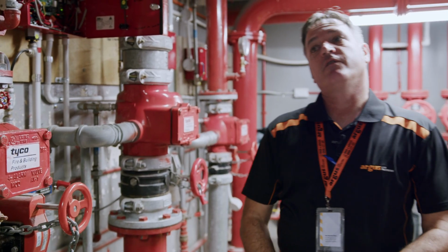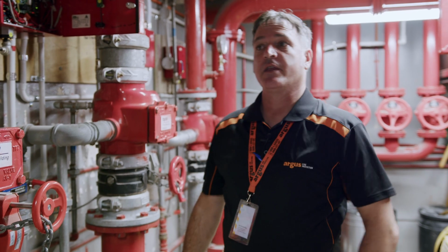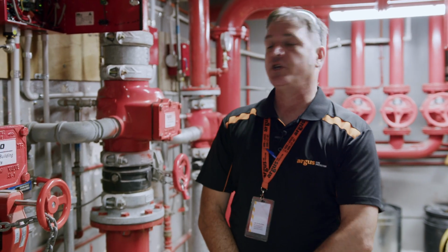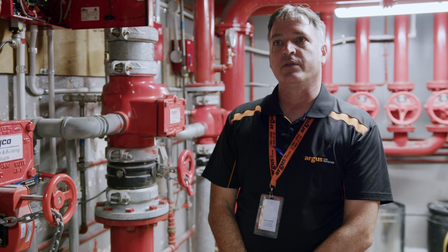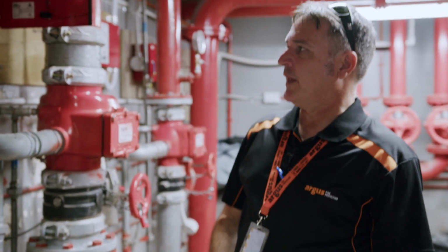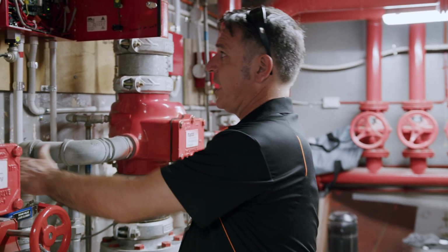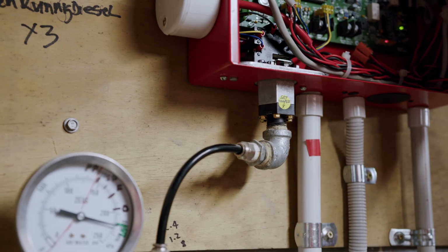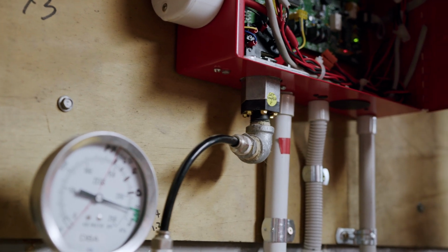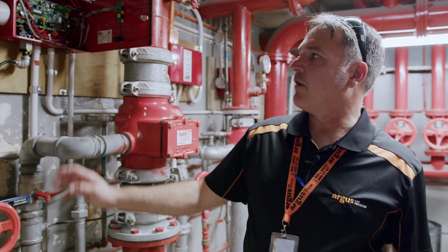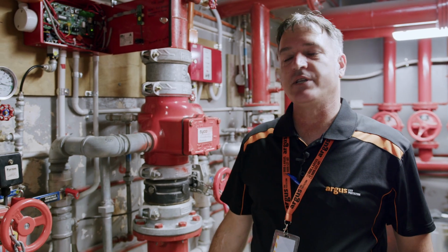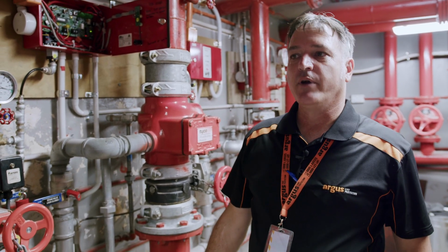Once we have checked and confirmed the monitored valve is signalling the DBA, we will then move on to check our pressures within the system. The most common and easiest way to check that our pressures are correct is through what we call the quick test gauge, which is located here and is off a little pressure switch running from the DBA. Once we have confirmed that our fire pressure and our defect pressure are set correctly, we are now ready to test the gong.